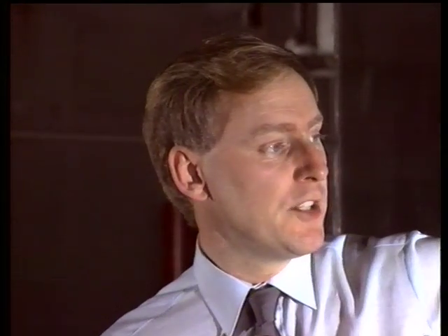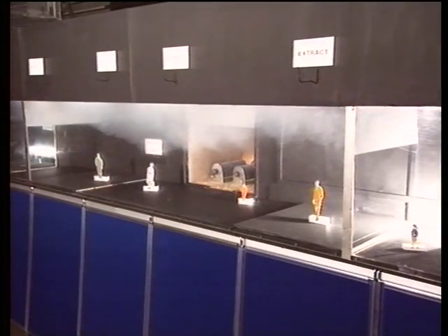And fourthly, and it's something which we can't show on the small scale, we've done it on large scale, you need sprinklers within the fire room actually controlling the fire. So the sprinklers may not put the fire out, but they will actually control it and limit the amount of smoke entering the mall. For large undivided volume buildings, all these measures must be applied, or the system will fail, as can be demonstrated by reducing the effectiveness of each feature.